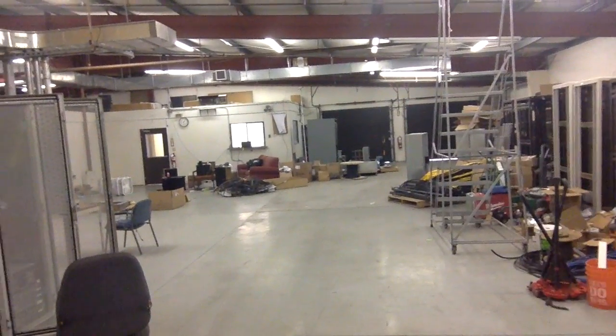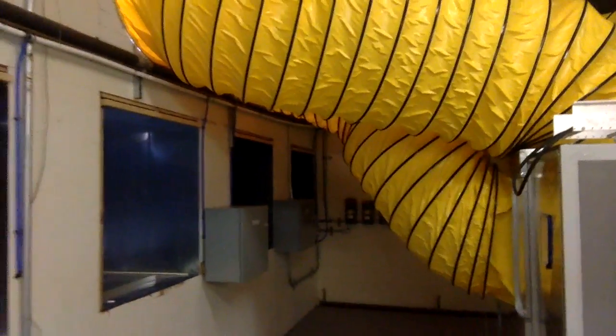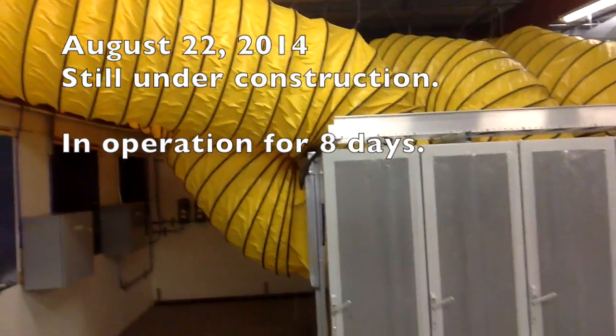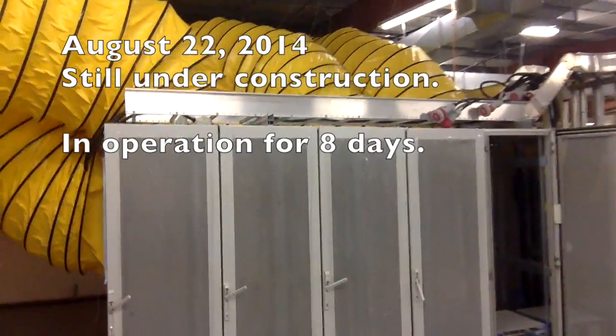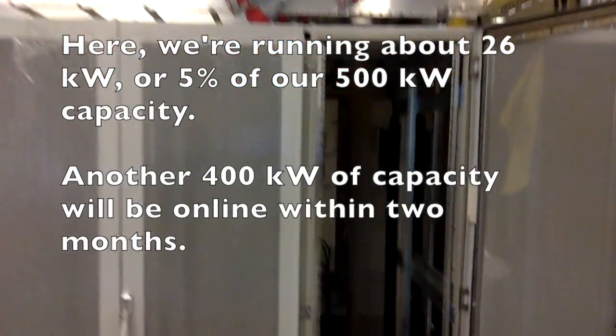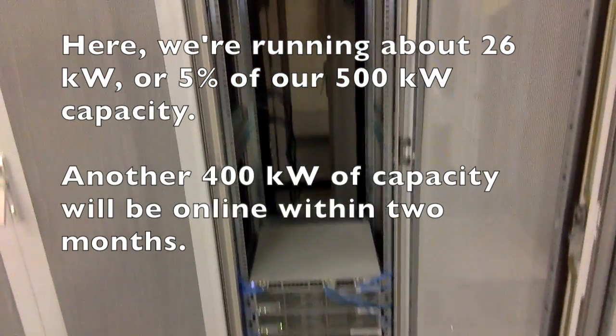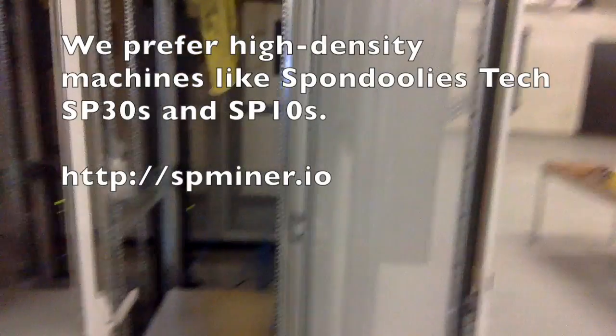Over here, we have our cooling system itself for the racks and pod for our system. It's a hot air containment system, so all of the hot air gets sucked straight up outside through those big yellow ducts. I'm going to run outside for a minute and get a temperature reading for what the air outside is right now. So right now we've got 25.8 degrees outside. This is a medium temperature summer day.